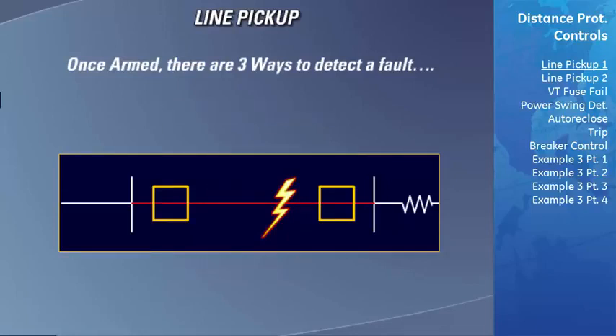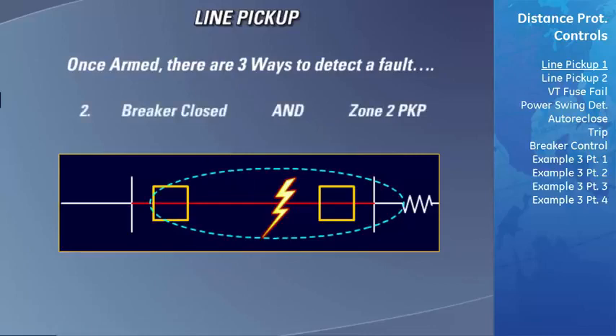The second method the line pickup element uses to detect a breaker closing in on a fault is by first identifying that the breaker is actually closed. This is done by monitoring the status of the 52B contact or by detecting some current or voltage on the transmission line. Once the breaker being closed is established, the second criterion is that the D60 must detect a fault within its Zone 2 area of protection. Both of these conditions must be true to cause the D60 to trip. Zone 2 is used instead of Zone 1 so that we can be sure that the entire transmission line is being monitored for this fault.